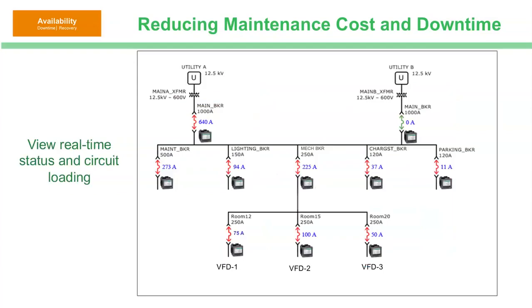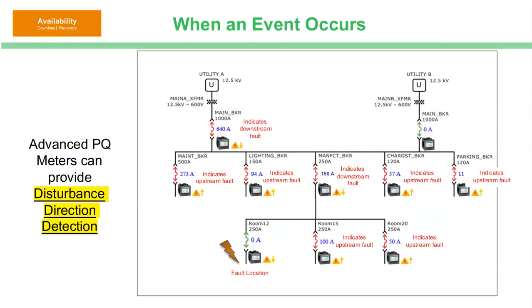So in a monitoring system, it's very typical that you'll be able to see the real-time status of your system. So you'll be able to know, are breakers open or closed? What's the loading? Are there any issues? And one of the very cool things about a monitoring system and the disturbance direction detection that I mentioned earlier is that when a disturbance does occur, it'll actually point you to where the problem happened.